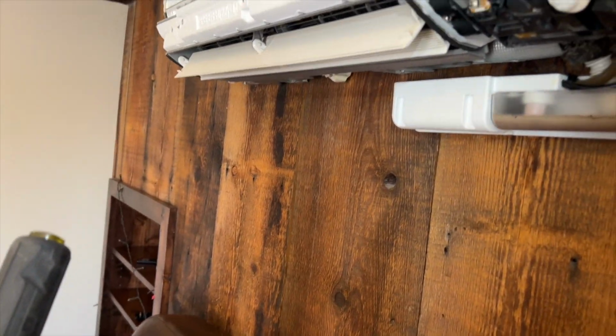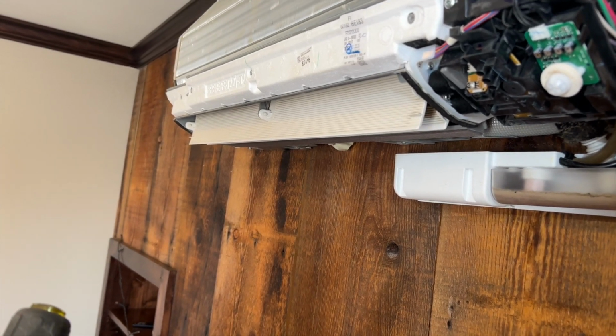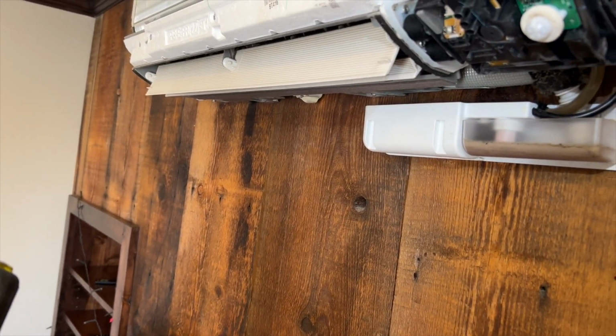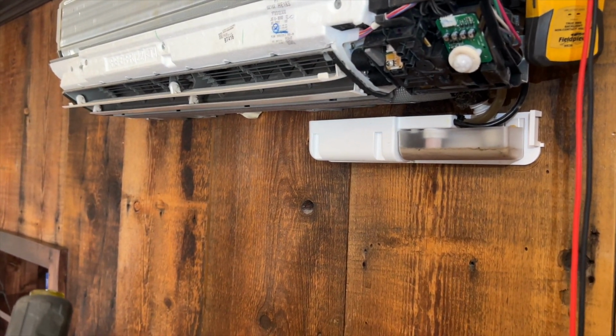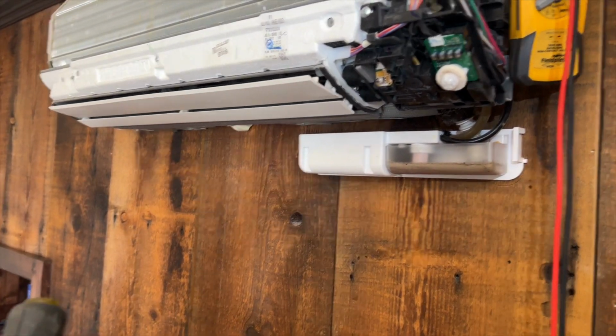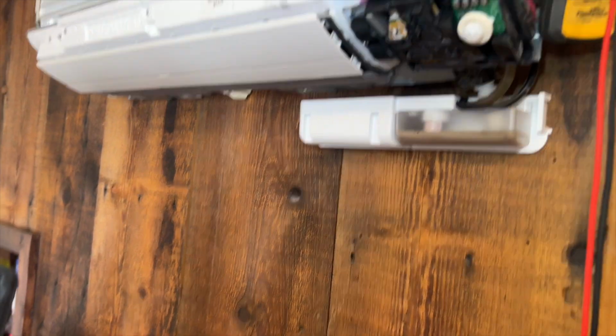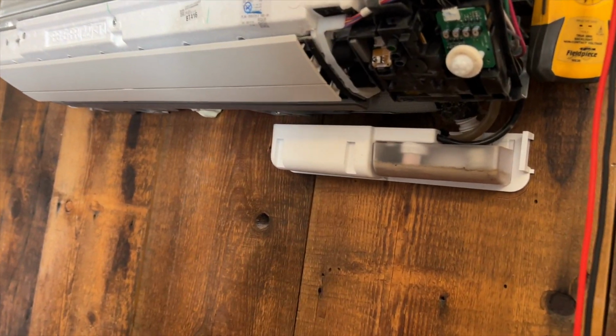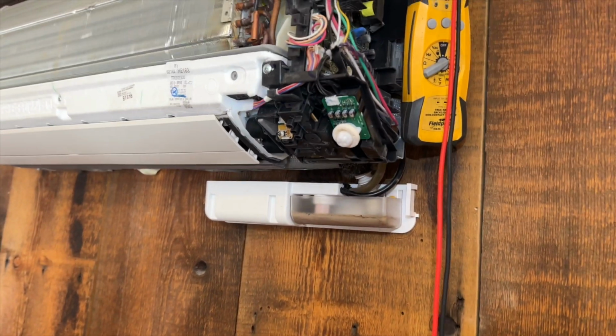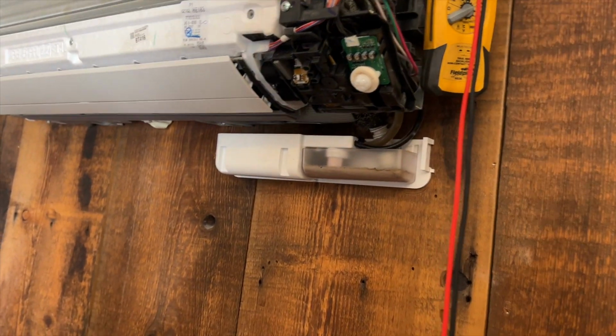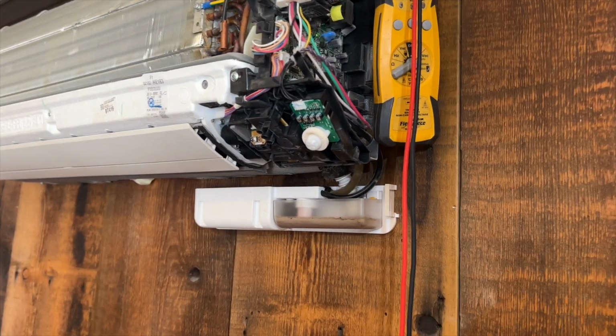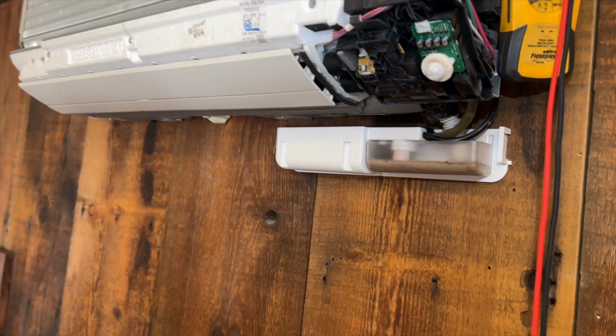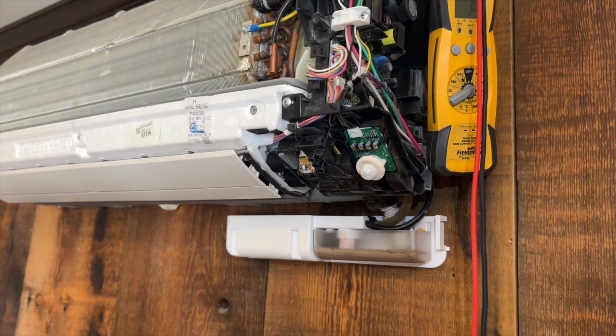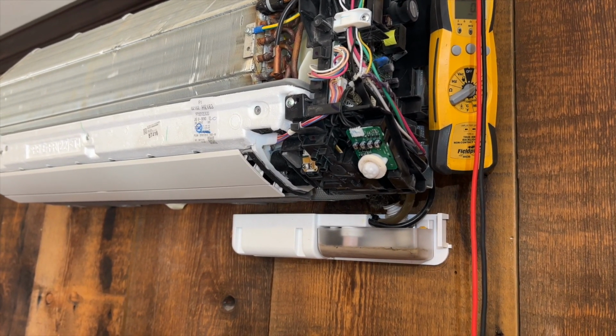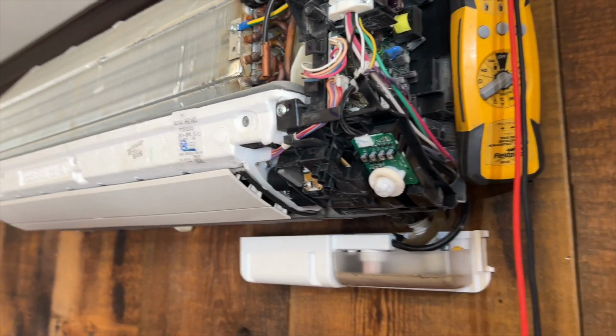Yeah, so I would say there's something definitely messed up with our fan. Yeah, it's giving us an error code now. So I would say that we probably have a problem with the motor because all the voltage seems to be fine, except for that one voltage, which was the motor control voltage. It's supposed to be at 15. It was like 10, 11, but yeah, I was really hoping it wouldn't be the blower motor, but that's going to be a total pain to replace.